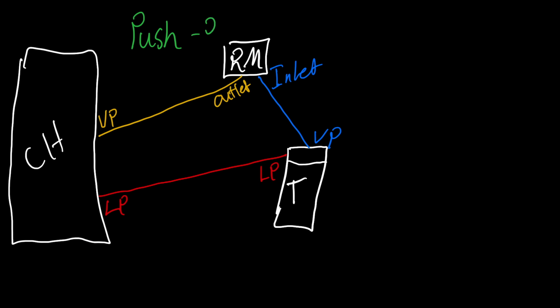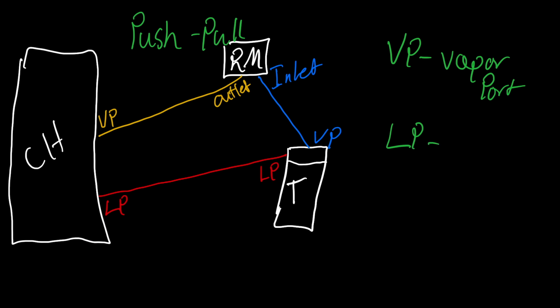We're pulling the vapors off of that tank, making the pressure drop in the tank enough that we have a pretty high volume, and our tank pressure never builds like a normal recovery would, because we're drawing the vapors off. So we stack that tank full of liquid, and pump all the vapor back into the chiller, which isn't going to cause any issues.